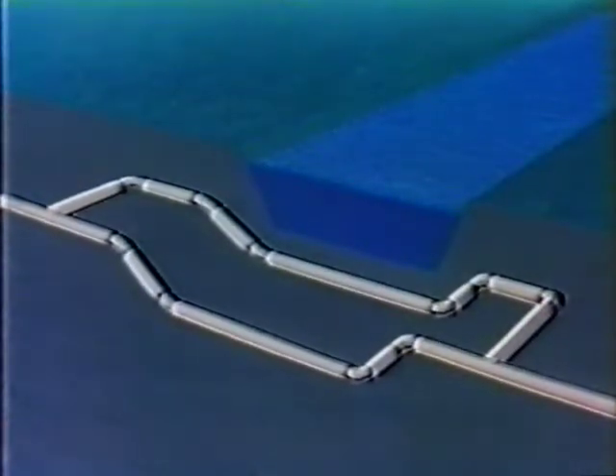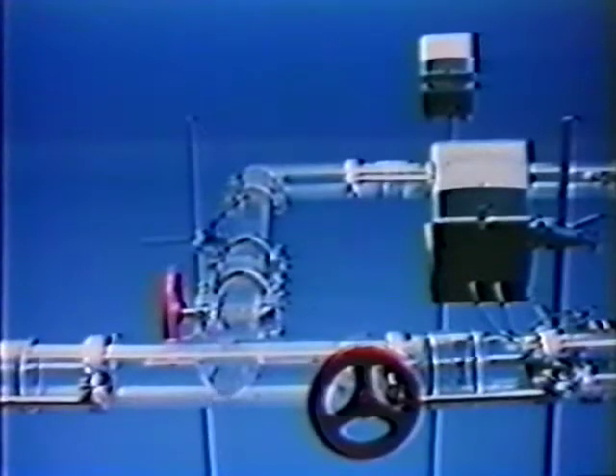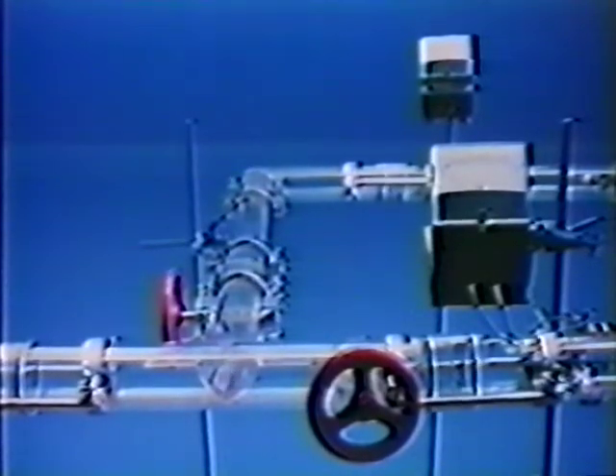In view of the route preference mentioned, it follows that any condensate formed at the beginning of a regional pipeline network will generally flow to a single terminal branch of this network. It's possible to calculate to what offtake points the condensate is likely to be carried, where appropriate measures can then be taken. A special case of route preference occurs with large double underwater crossings. Each leg of the crossing carries 50% of the gas stream. Route preference causes the liquid to flow to the reserve leg, where it accumulates.